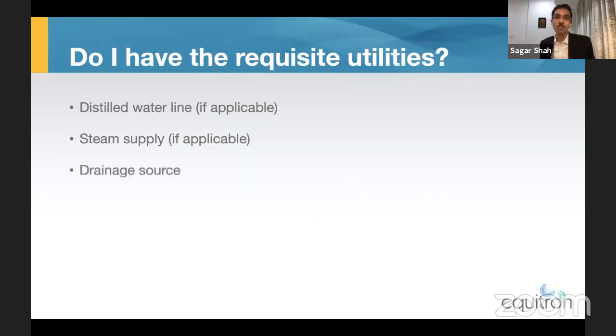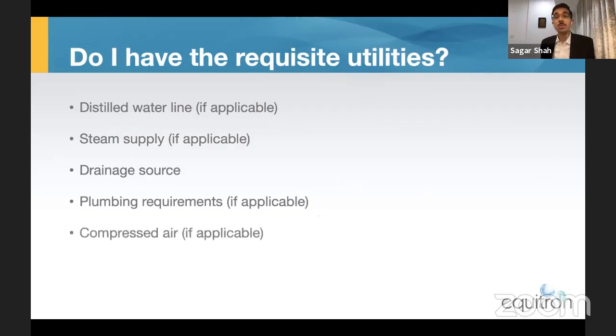Also, when it comes to the drain source, it should be pretty close to the autoclave, typically not more than 4 to 5 feet away, but that's something that you would need to check with the manufacturer. And sometimes because of this, you might also need to undertake special plumbing jobs in order to install and operate the autoclave. Some autoclave models also need compressed air supply, so that too is something that you would need to look at. And finally, depending on the size and heater capacity of the autoclave, you also need to consider whether the autoclave requires a single phase or a 3-phase power supply. Is the wiring in your lab sufficient enough to handle the requirements of the autoclave?